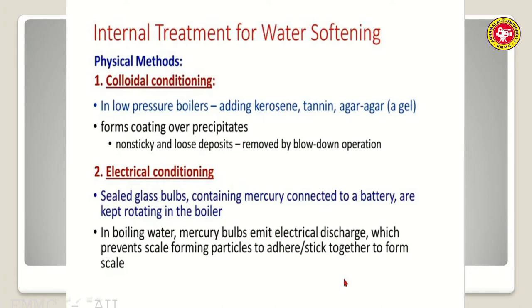Physical methods: Colloidal conditioning - in low pressure boilers, adding kerosene, tannin, or agar-agar (gels) causes them to stick with loose deposits of hardness-producing substances, which settle at the bottom and can be removed by blow-down operation. Electrical conditioning: sealed bulbs containing small amounts of mercury are connected to an electric charge; the mercury continuously emits electrical discharge, which prevents scale-forming particles from adhering to the inner surface of the boiler.